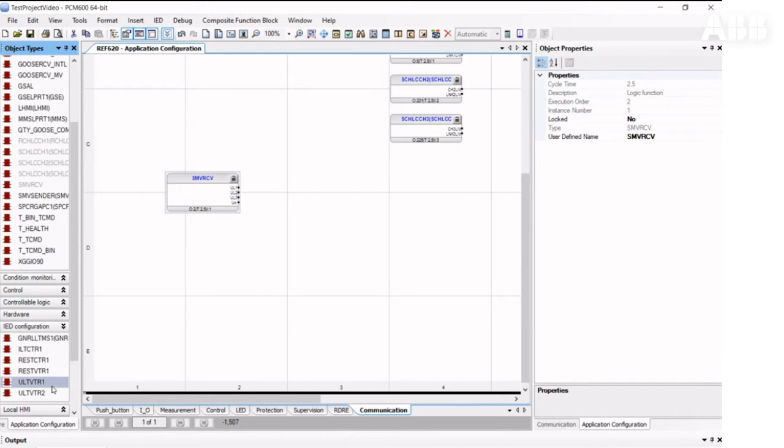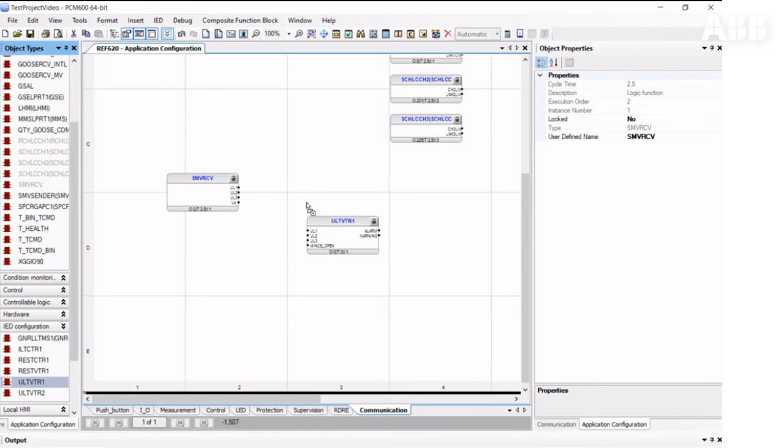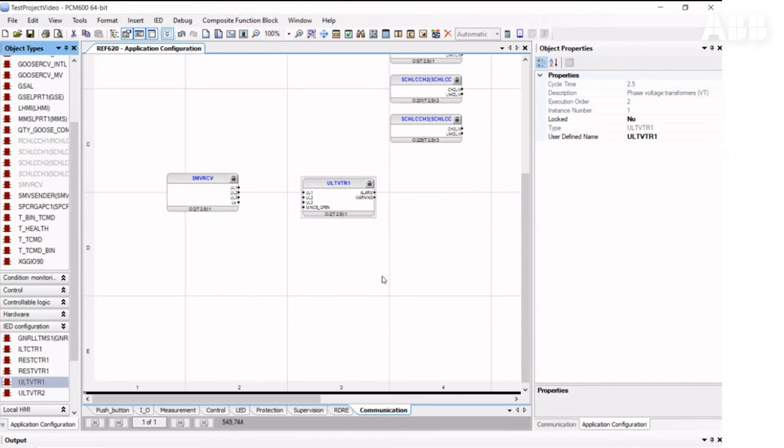This may be ULTVTR1 for receiving three-phase voltages, or ULTVTR2 if you need to assign only one-phase voltage for SynchroCheck logic. In this case, we want to receive three-phase voltages.